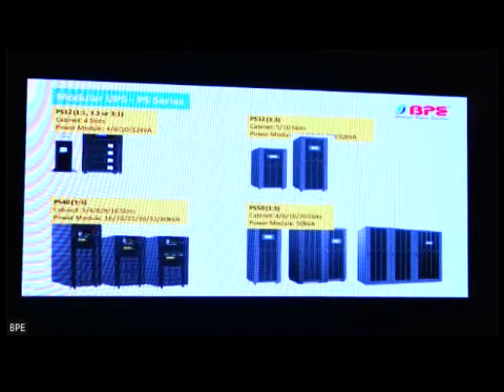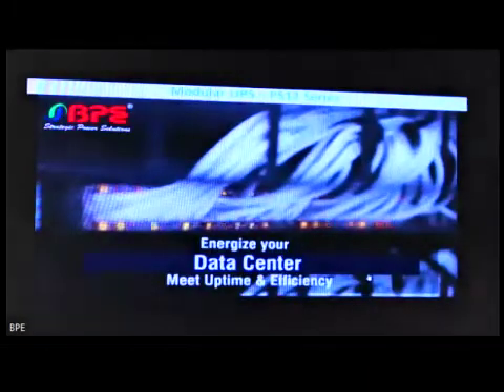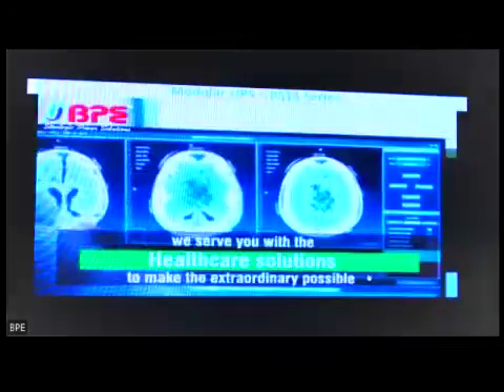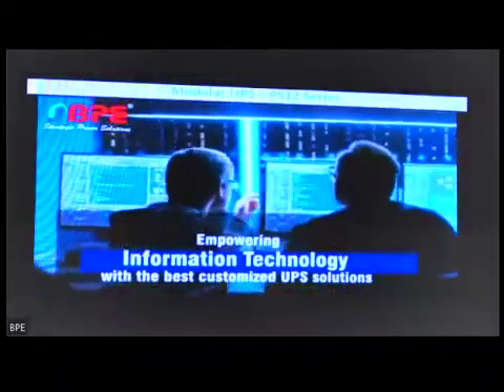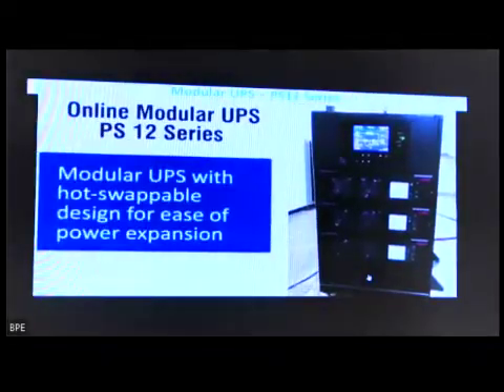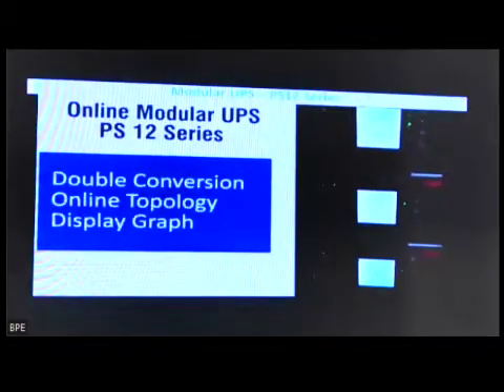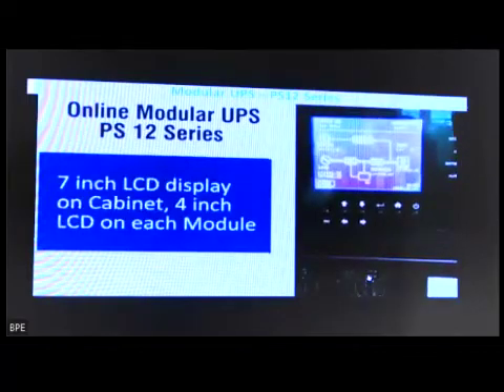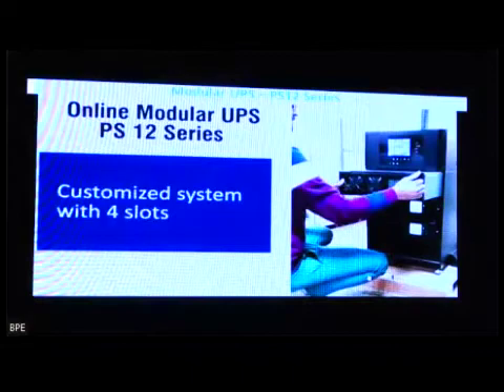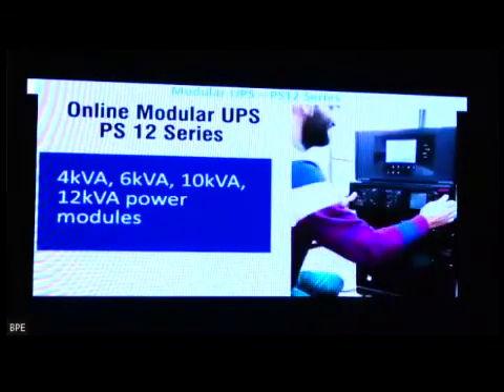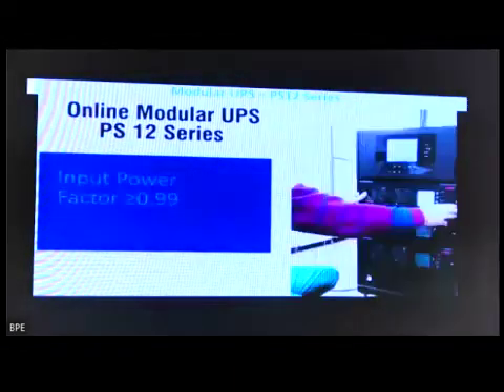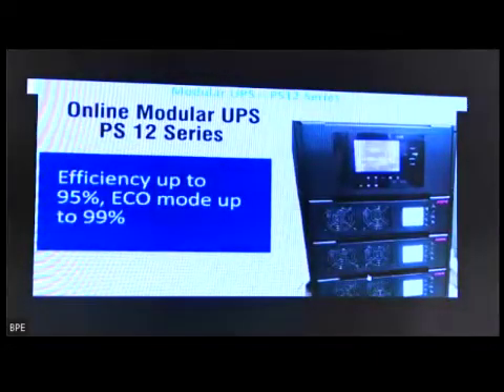Then we have PS32 with 5 and 10 slots, and the PS40 series with 40 kVA power modules, starting from 16 kVA. And lastly, we have the PS50 series with power modules of 50 kVA, 50 kilowatt. All the modules are unity output power factor, so kVA is equal to kilowatt. So there is a video of the PS12 series to give you an inside idea about the product. Hot swap power modules.